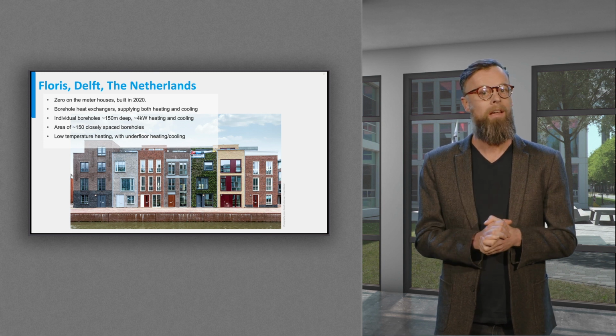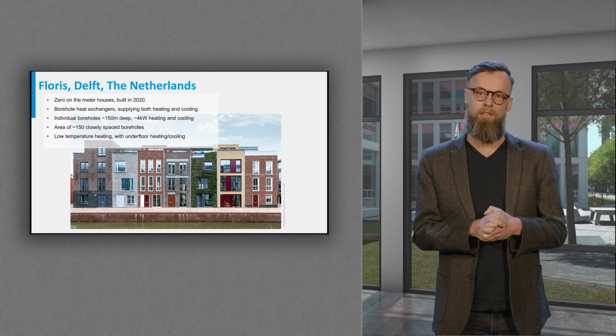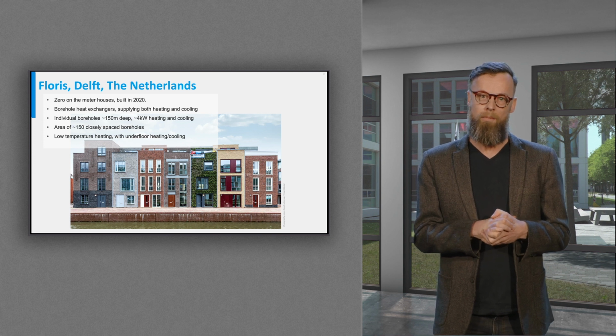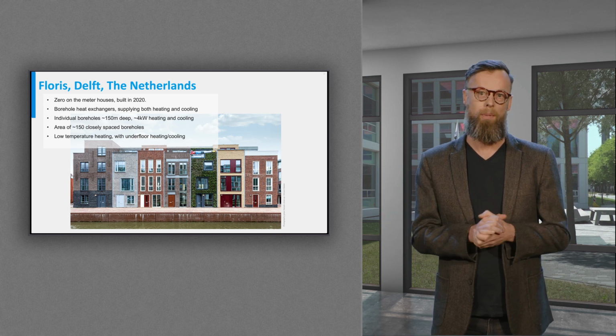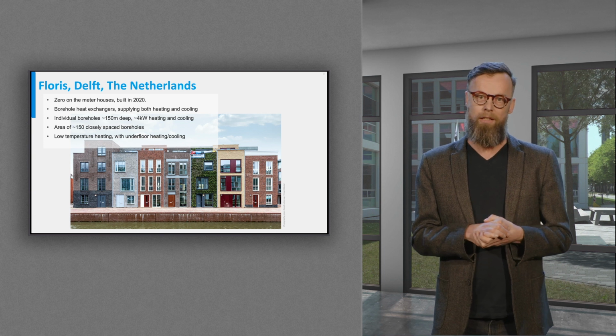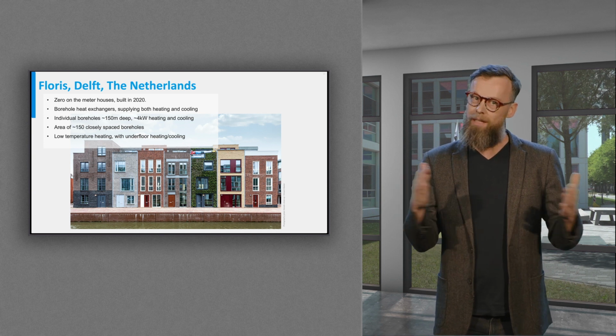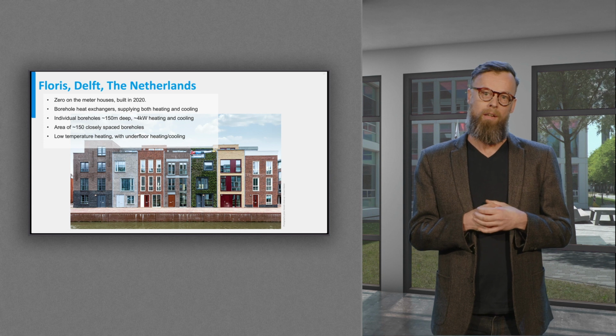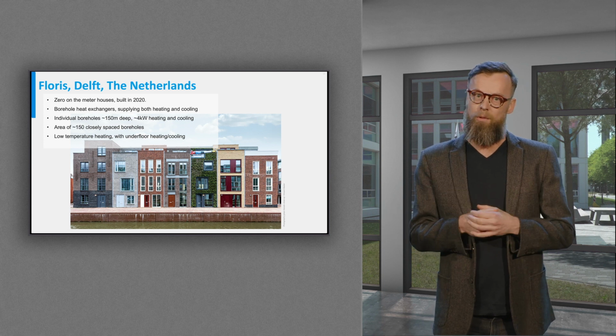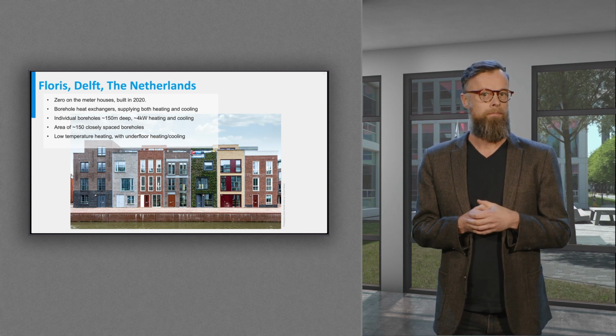In this neighbourhood, there's around 150 systems spaced closely together, between around 5 and 10 metres apart. Care needs to be taken during the design to ensure that the systems don't interact with each other. Balancing the heating and cooling loads throughout the year helps with this.